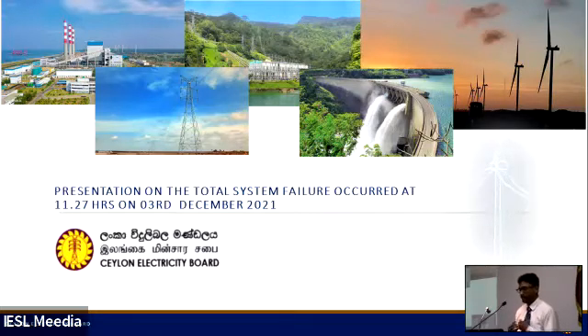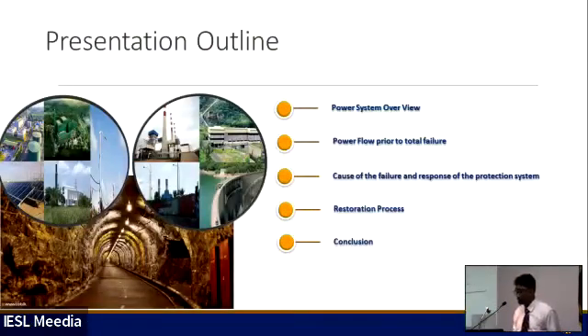So, first of all, I will briefly explain the pre-fault situation of the system and what happened during the fault. Then Engineer Vettasinghe will carry out the analytical part that we have done, followed by myself again, on the restoration process. Due to the time constraints, I will just brief through the presentation. The content is as follows: an overview of the present power sector and the power flow before the failure, basically a snapshot of the system, the cause of the failure and response of the protection scheme, then the restoration process.